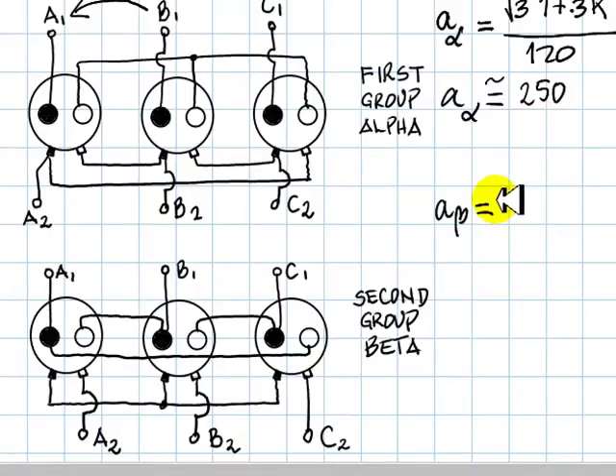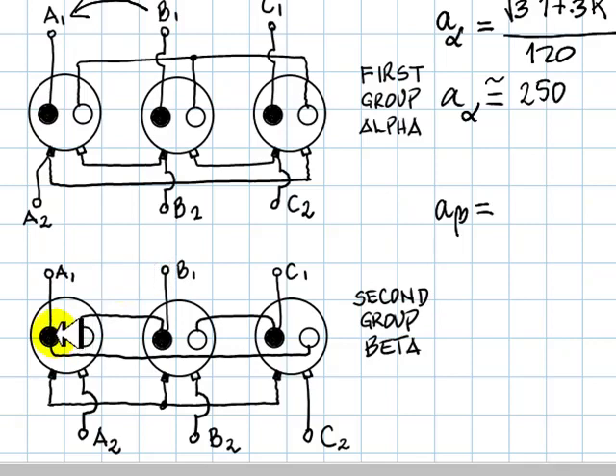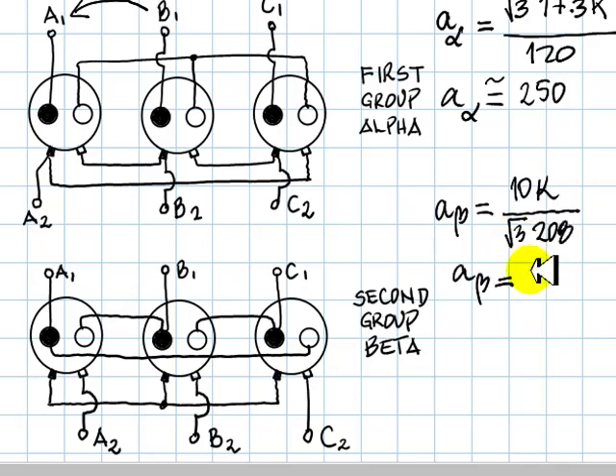For Group Beta, the primary line-to-line voltage equals the coil voltage: 10 kV. The line-to-line voltage of the secondary, connected in Y, is root 3 times 208 volts. This ratio is approximately 27.8.